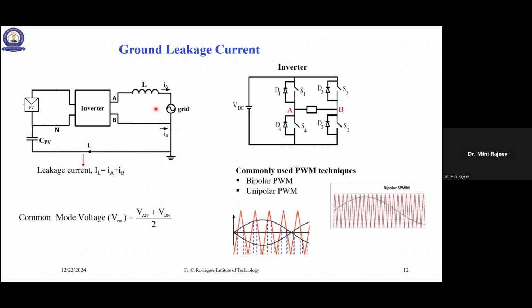Okay. And there are two currents in this, like in op-amp circuits, which you must have studied: common mode current and differential current. Similarly, there is common mode voltage and differential mode voltage here. Differential current means a current which flows like this and goes back, IA minus IB you can see. Common mode current is IA plus IB. So this common mode current will flow through this capacitance, through the system. And why is this current happening? The common mode voltage definition is (VAN plus VBN) by 2. Here we are taking A and B as the terminals of this inverter.